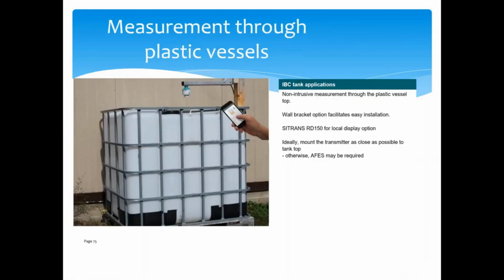Really want to talk about this one. It's something that has gained popularity and traction over the last couple of years. Since radar transmitters are looking for a change in dielectric, depending upon the plastic material of my tank, I can mount a radar outside of the tank and penetrate directly through that plastic material. This only works with plastic, and only certain types of plastic that have a low enough dielectric. But if you're dealing with a plastic tank, and you want to mount something outside the tank, either for compatibility with what's inside, or you don't want to give up head space due to blanking distance, this is a good solution. Keep in mind we can only do that with radar.